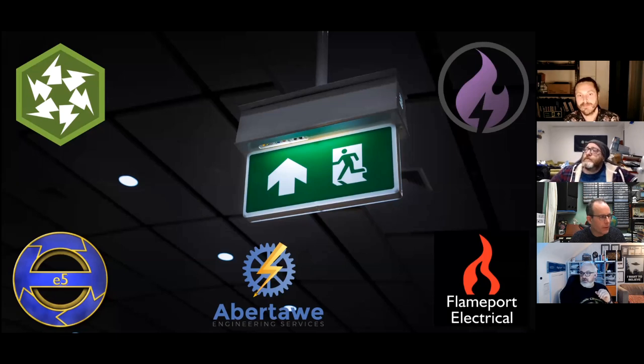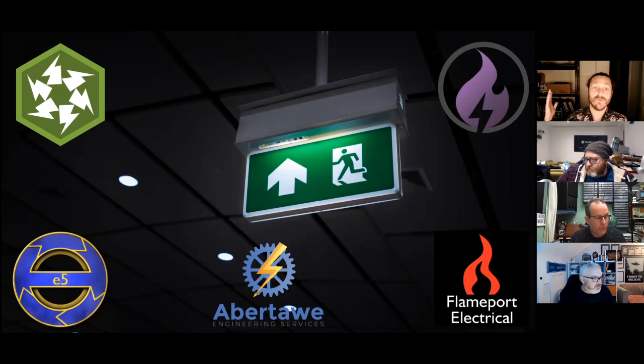Moving on. Right, Mark Holmes again asks, where a conventional system is wired in 4-core FP200, 2 cores for detectors and 2 for sounders, does this still comply with BS5839 Part 1? So what he's saying is that you've essentially got a circuit for your zones and a circuit for your sounders. Years ago people used to wire 4 cores everywhere. Nowadays you've got 2 wire systems, so you can put sounders on the zones. So that's not needed. The problem is, if that one 4-core was cut, you're going to take out 2 circuits. But the standard talks about zones and sounders as separate. So I would say if it was installed like that, it complies.